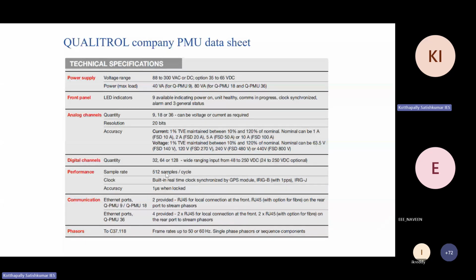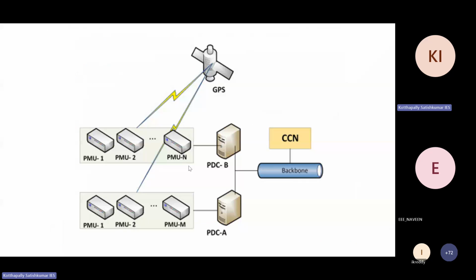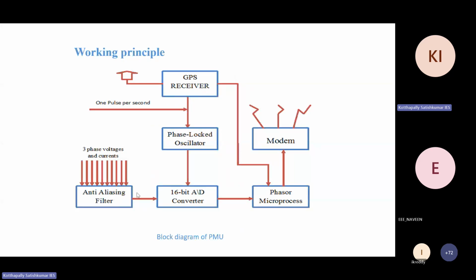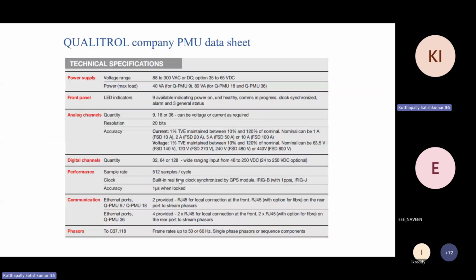Performance, sample rate. As I told, we take the samples from the inputs. Here, as I told before, this PMU takes the inputs from three-phase voltages and currents. So you give them to an anti-aliasing filter before the sampling. Here the sample rate you can see is in the range of 512 samples per cycle. As we have a 50 Hz power system, each cycle is 20 milliseconds. So in each 20 milliseconds, this PMU takes 512 samples. In one sine cycle, you are taking 512 samples. So you can understand the accuracy level and the speed of data it will report to the control centers. Now, the accuracy of the PMU is 1 microsecond when it is locked.